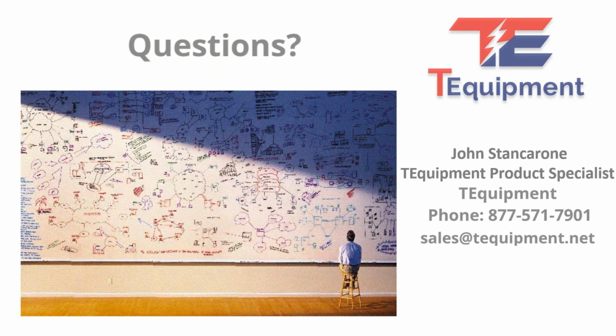One more question. How often should insulation resistance be performed in a photovoltaic system? As I mentioned at the end, doing the test periodically will help you gather information to determine if the insulation of the system is degrading or not. I mentioned a couple of standards, and one of those standards was showing the schedule for the maintenance. Condition 1, which is basically that everything is good, was showing 60 months, which is a lot of time. So you don't have to do that often.